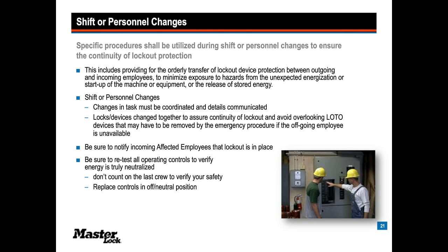The incoming crew should go through and identify that the proper isolations have been made and make their own test and verification to assure that they are indeed taking on a safe working condition. Okay, so very important to take personal responsibility for that testing and verification when you're coming on duty.